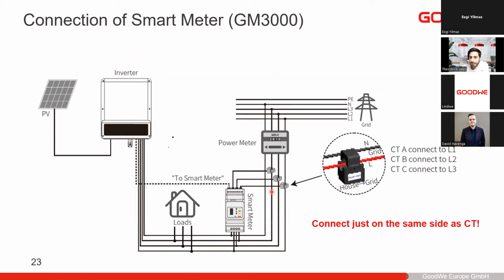Make sure that you install these CT clamps just before the grid connection point, so just before the main house electricity meter. So not after and not before the loads here or anything like this. They should be just at the grid connection point, because these will measure the energy flow here. So in case you need to limit the export to the grid, then these are the sensors to know how much energy is flowing in and out to the grid.